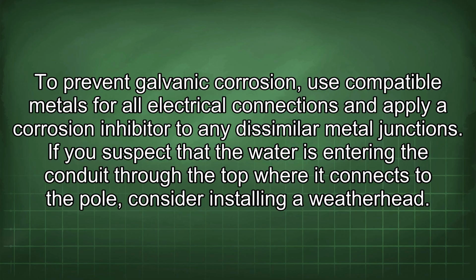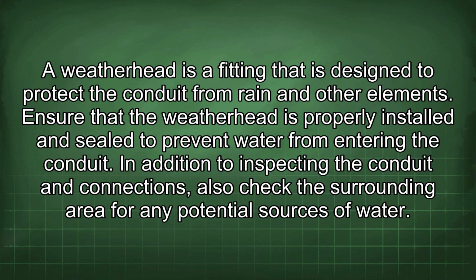To prevent galvanic corrosion, use compatible metals for all electrical connections and apply a corrosion inhibitor to any dissimilar metal junctions. If you suspect that the water is entering the conduit through the top where it connects to the pole, consider installing a weatherhead. A weatherhead is a fitting that is designed to protect the conduit from rain and other elements. Ensure that the weatherhead is properly installed and sealed to prevent water from entering the conduit.